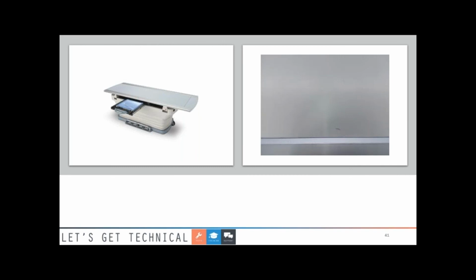All right. So if all that's good, it's time to take a next step. Now, if you have a digital system with a detector, you're going to want to make sure that there are no dents, scratches, or contrast, or any other media on the table. There's something called a barium shield underneath, which is supposed to keep stuff off of there. You're also going to want to check your wall stand. If in doubt, I'd clean the surfaces because those dents will show up. And if you calibrate, then it's going to show up forever. So anything that's wrong is going to show up. Now, I've had a lot of people ask, well, what about discoloration and stuff? That usually isn't a problem.